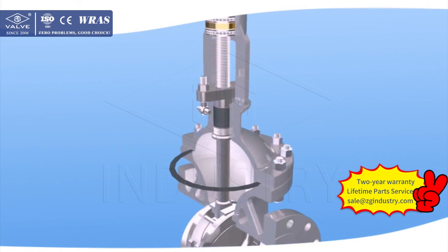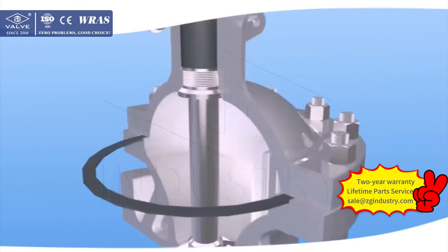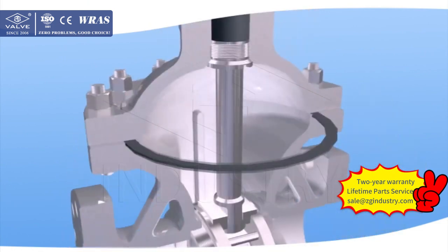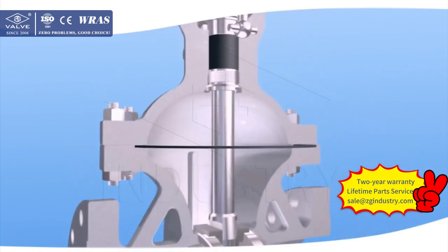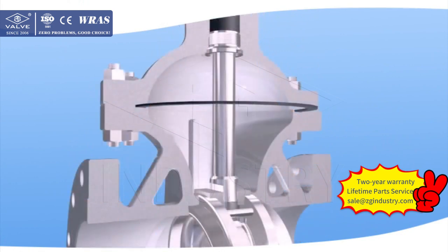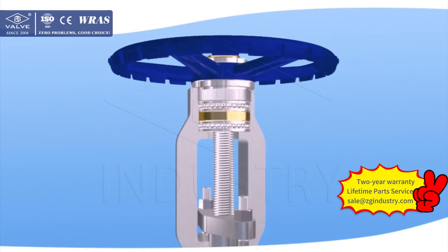6. Top entry nut design assures that when the valve is open, even if the hand wheel is demounted, the stem and disc will not fall down. The stem nut is made of aluminium bronze, and both sides are set with bearings. All these make the valve easy to operate.